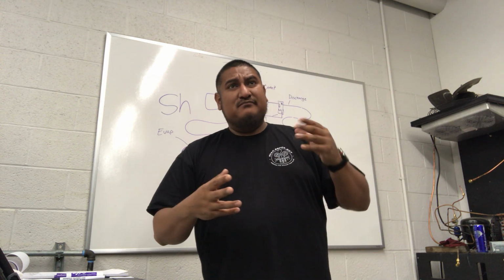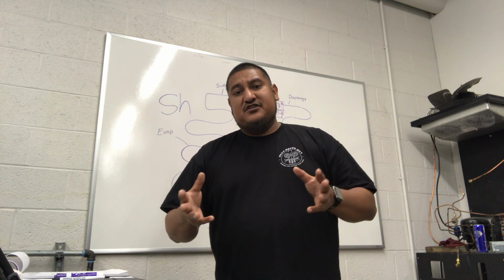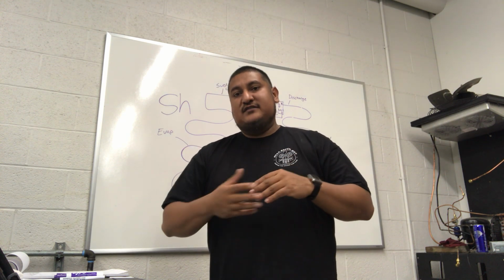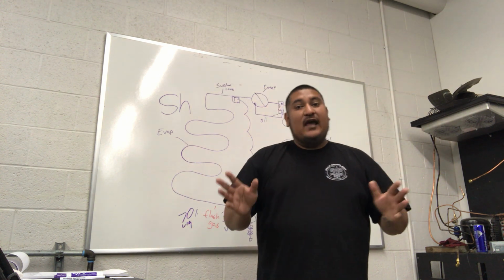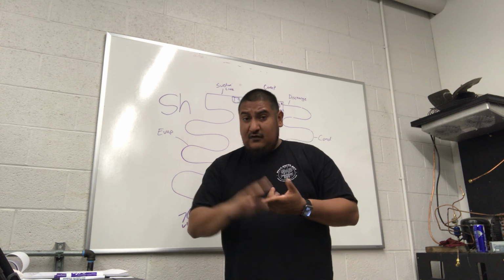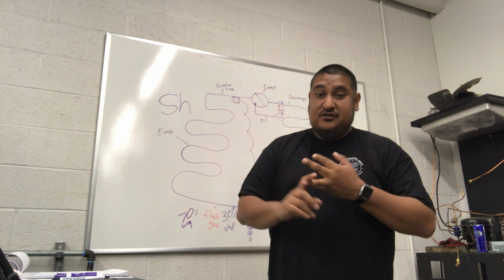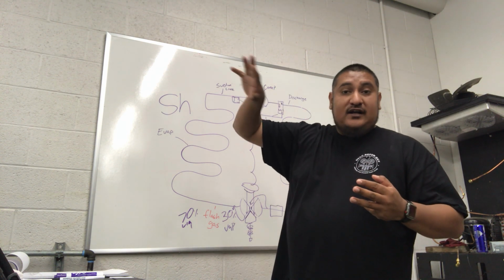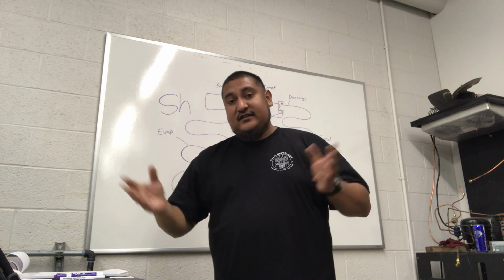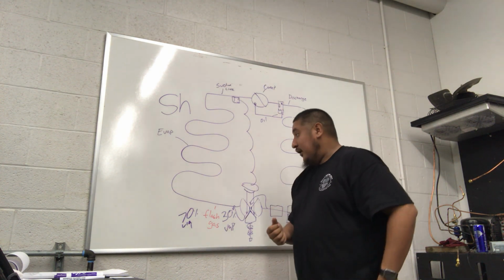It's actually about 20-30% of a unit's efficiency. When a unit's running very poorly, it's normally going to be an airflow issue. Airflow can do a lot of damage. It can freeze your coil. It can send liquid back to your compressor. It can give you a high head pressure, which is basically saying that this guy's overrunning. Nothing's cooling it off. It can cause a lot of issues in our trade, right?